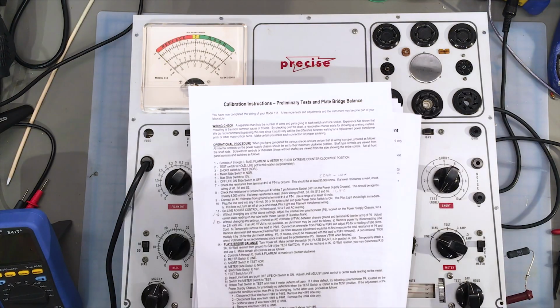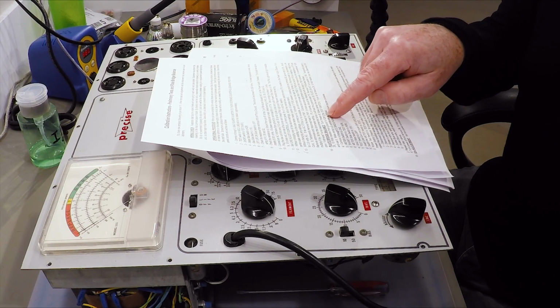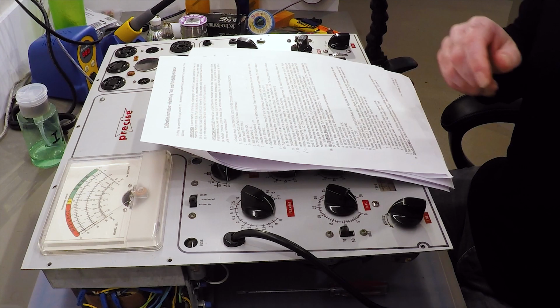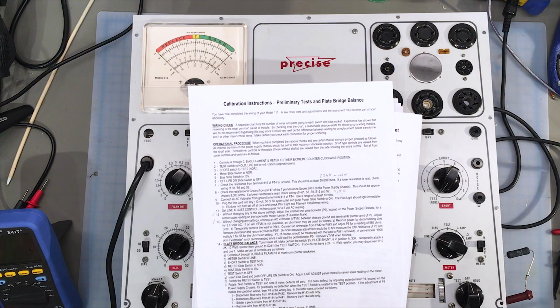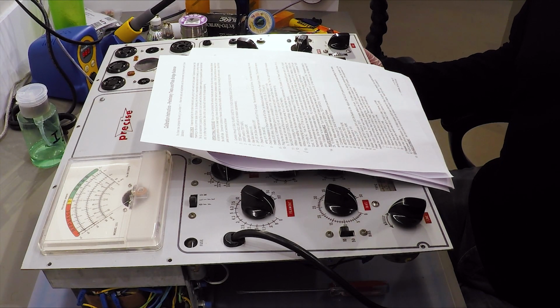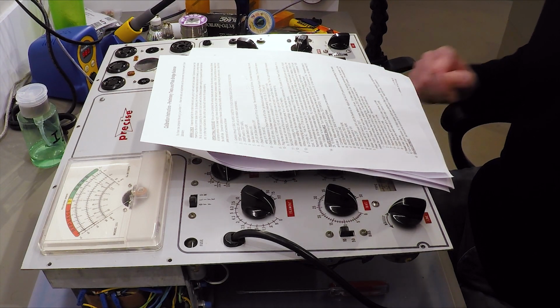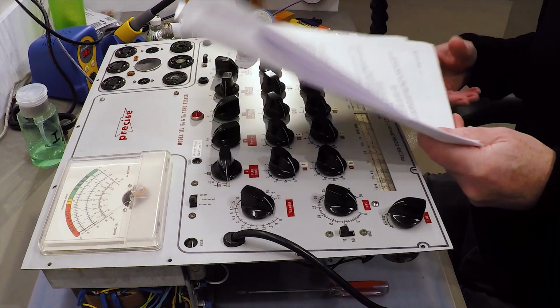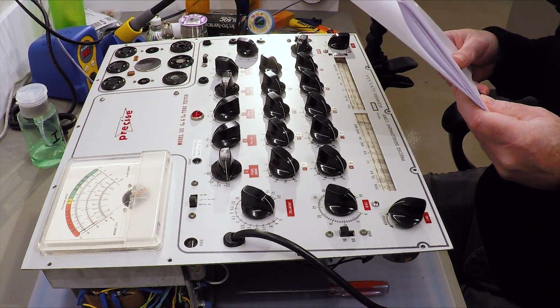It says switch to position 11, and this version of the instruction says switch to position 1. So that's just a cautionary note there. You do not want to attach this resistor to position 1. You want to attach it from ground to position 11. Otherwise, this step in the calibration will not work as it should.